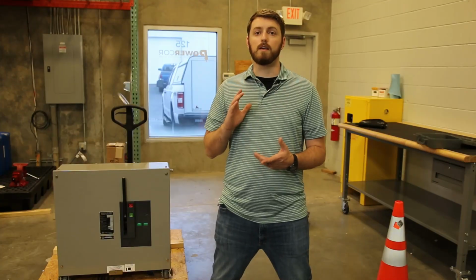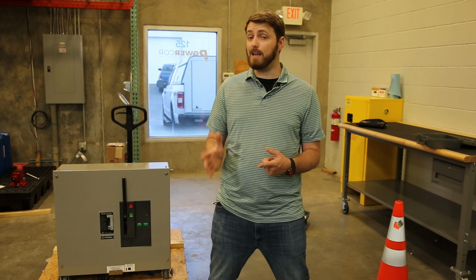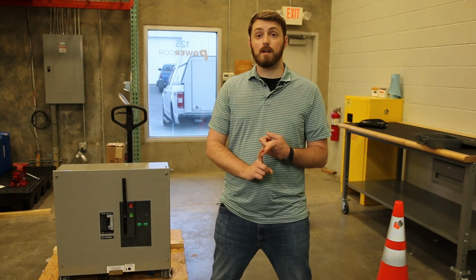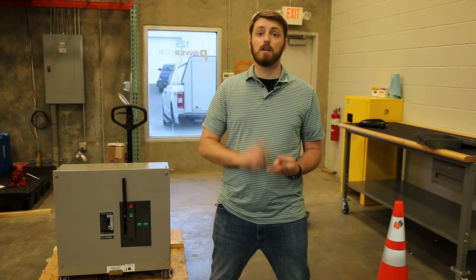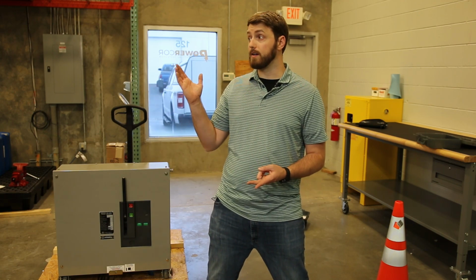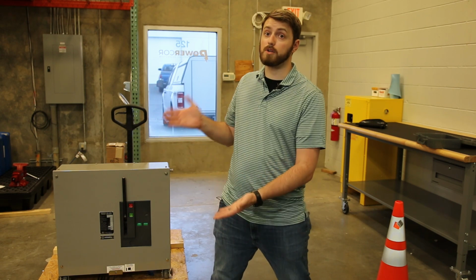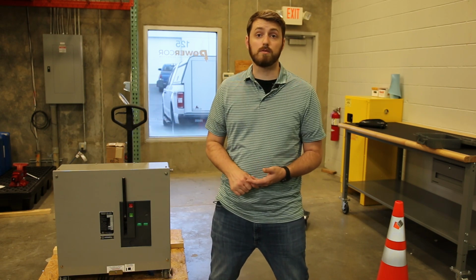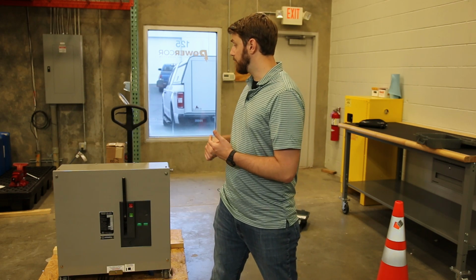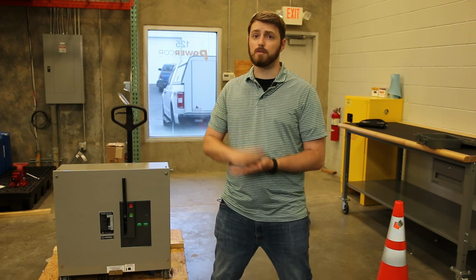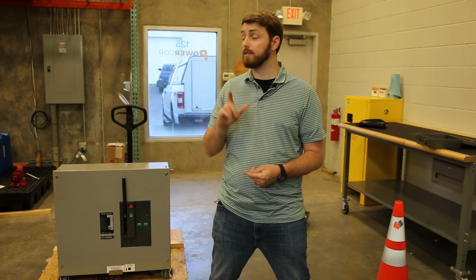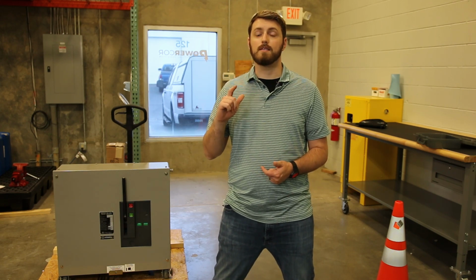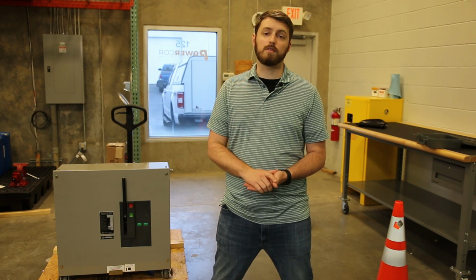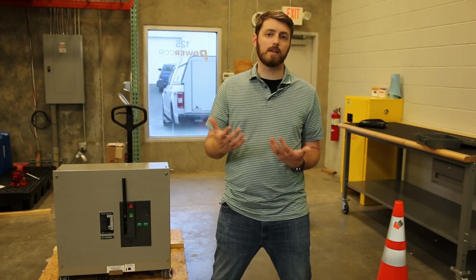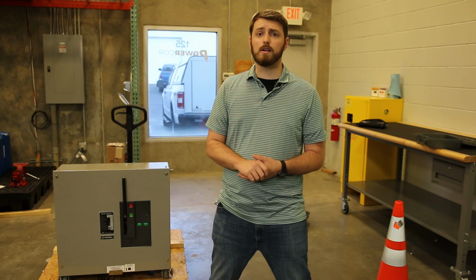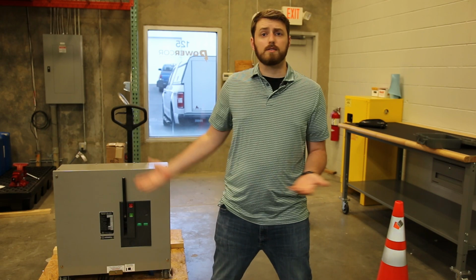That's really important. The electrical tests that have to be performed per NETA MTS on this breaker is it has to be measured, insulation resistance on DC. We're going to high pot per the manufacturer's published data. The operations and maintenance manual will tell you what values to high pot it at. We are going to perform the contact resistance test or the ductor test with the vacuum bottles closed. The last one, and the kind of tricky one that we have to do, is the contact timing test. So all 3 poles have to close at exactly the same time within a specified period. There's a couple other little minute things that we'll get into. Let's go ahead and get started.